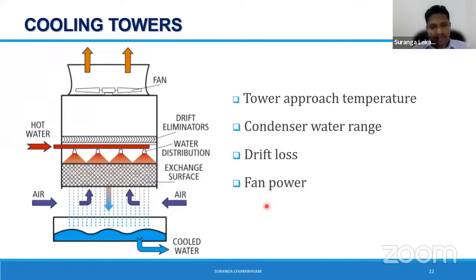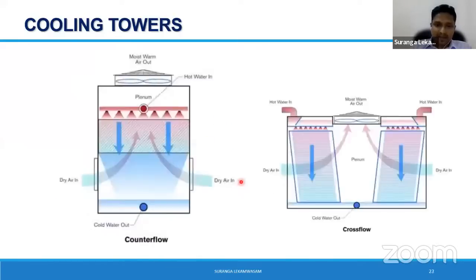I have actually done an exercise for a given capacity of a cooling tower. I could select motors from 22 kilowatt to 7.5 kilowatt. Do you believe that? So that's a vast range. So you have to specify this. This should be the motor capacity, or at least this should be my kilowatt per ton value for my motor selection. So you have to be smart, otherwise there will be issues like that.